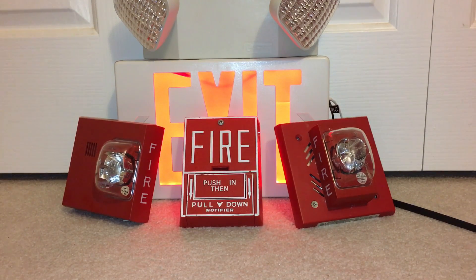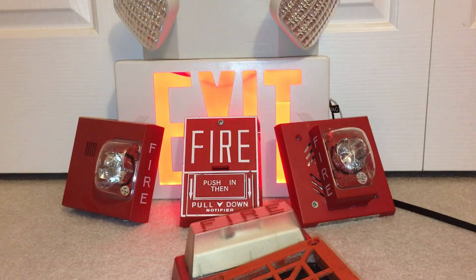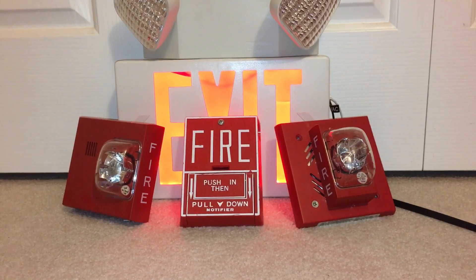And finally, bad or lazy installation. Say you had an original system with a Wheelock horn on a Simplex lite plate, and the horn broke down. The normal installer would take the plate off, take the entire unit off, adapt a new plate, and put an EH-DL1 on it. The lazy installer would just leave the old plate there and slap the EH-DL1 right over it and say it's done. That's lazy and I do not approve.